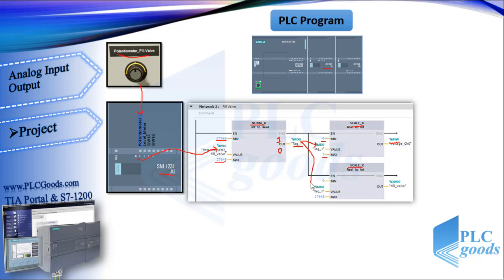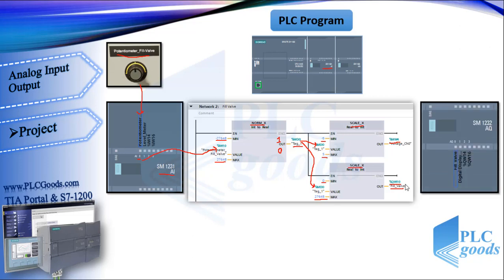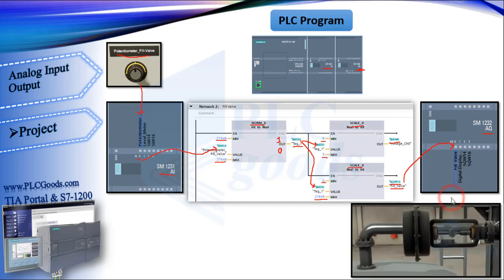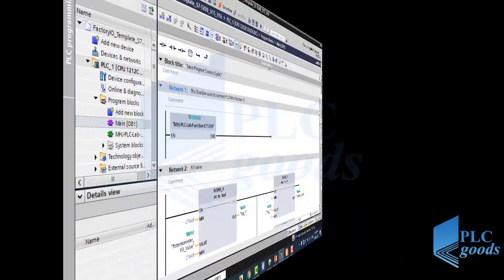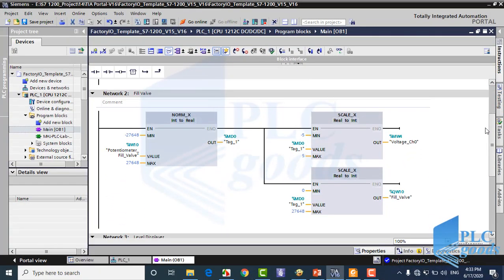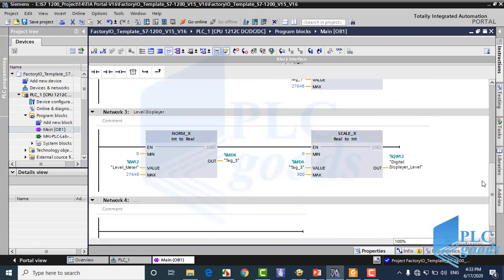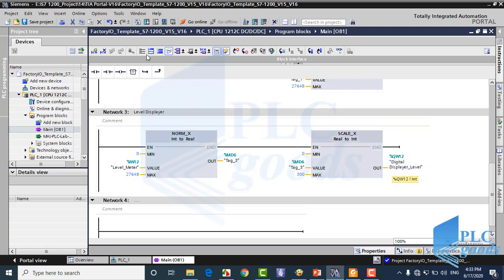This number will send to the first analog output. So, based on the S7-1200 manual, the analog output module will generate a voltage 0 to 10 volt to close or open the fill valve. All right, this is my PLC program. Similarly, norm and scale instructions are used to convert the level sensor signal to a number between 0 and 300, which represents the liquid level on the digital displayer. Let's transfer this program to a virtual PLC.